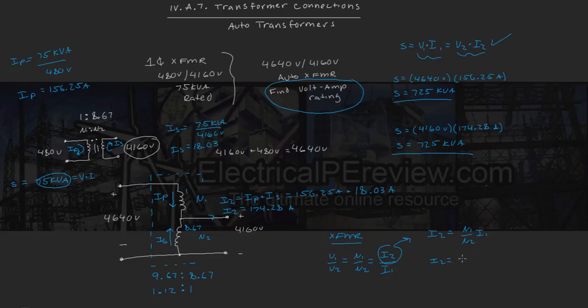We can plug this in as our new N1 we found to be 1.12, our new N2 we found to be 1, times our input amps, which is the same as our IP, which is 156.25 amps. We do the math and we come up with 175 amps, which is roughly the same as we found right here. How about let's try solving for our output voltage of our new autotransformer V2. We should come up with 4160 using our newfound ratio N1 over N2.